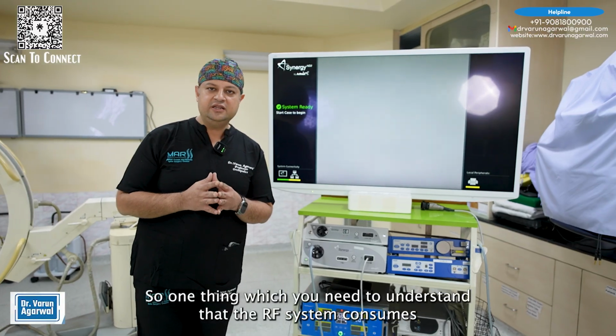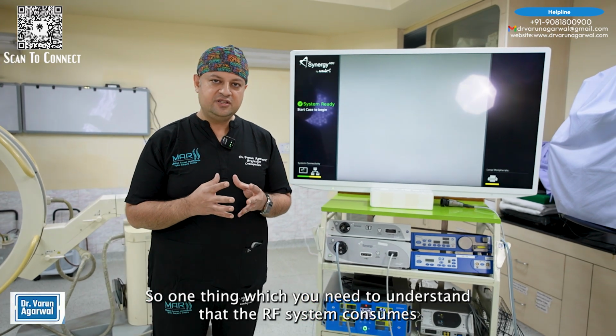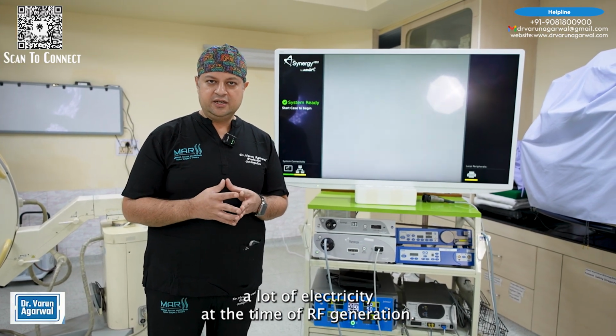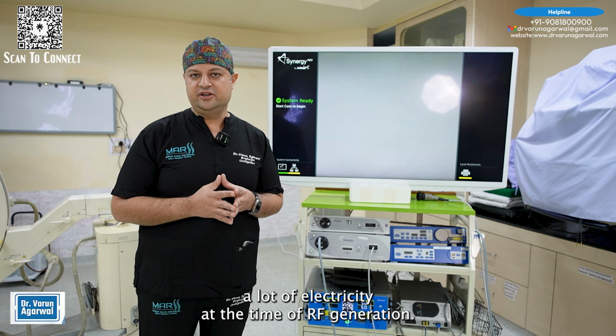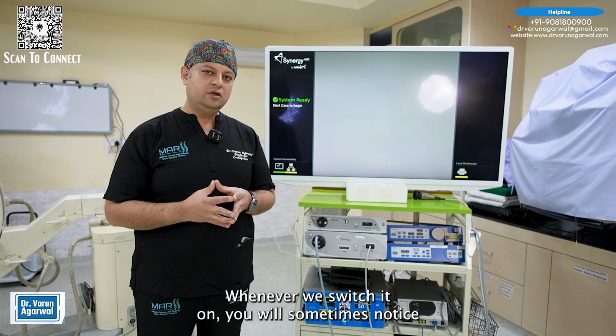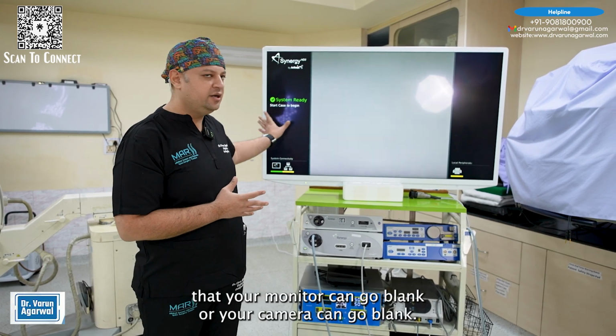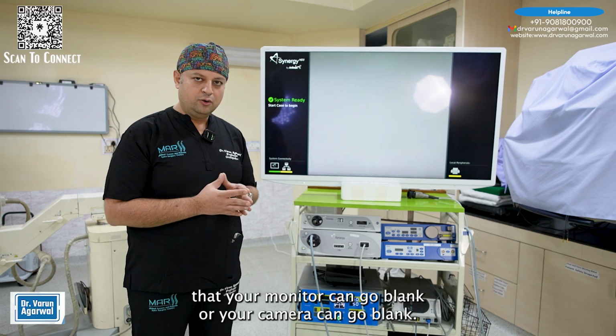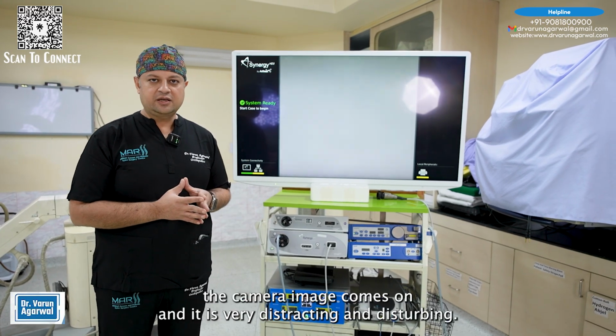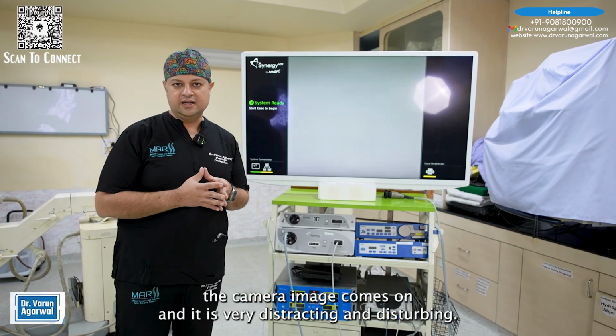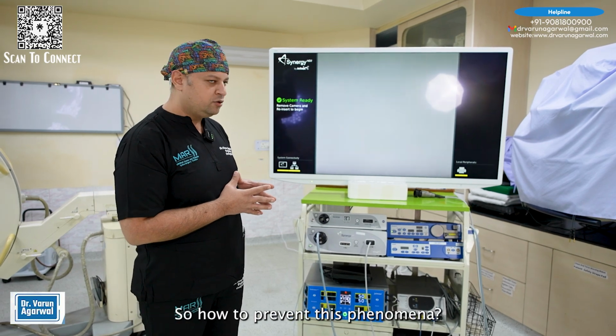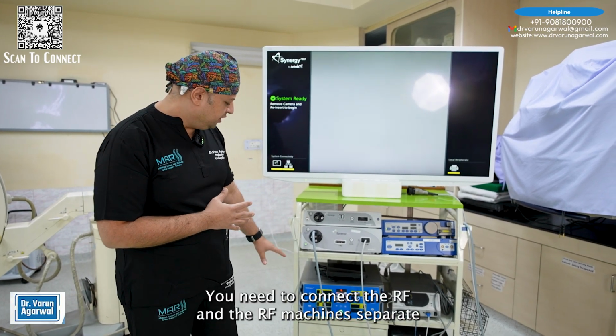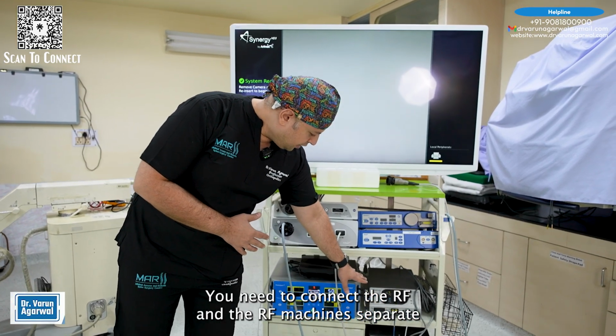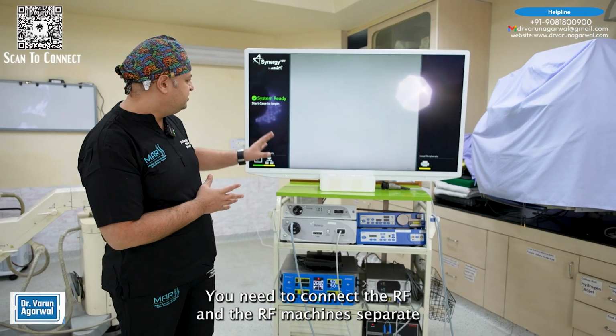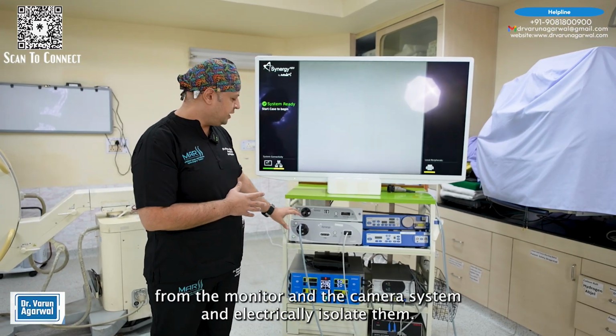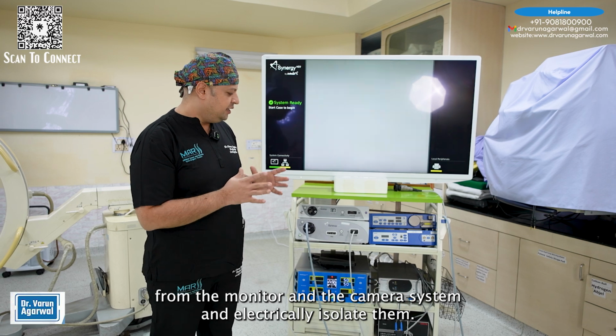So usually people connect their power supply thinking that the earthing which is there in this plug in this socket is enough, but we need to do a separate grounding of the medical devices using this point to the hospital ground. One thing you need to understand is that the RF system consumes a lot of electricity at the time of RF generation.